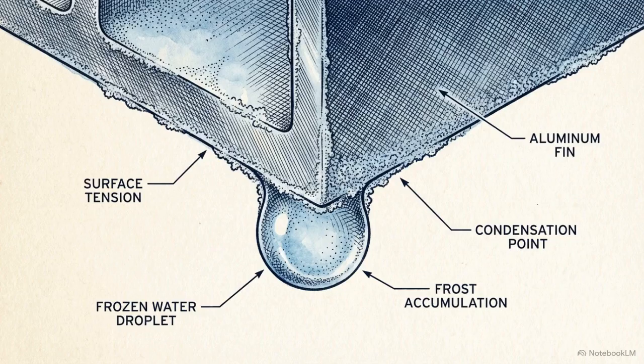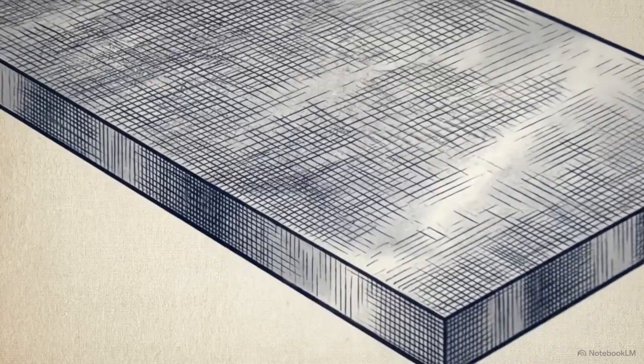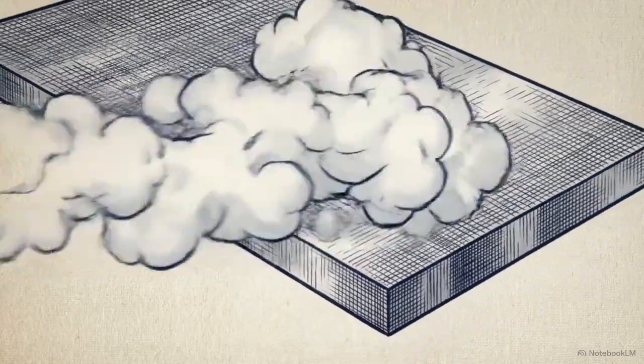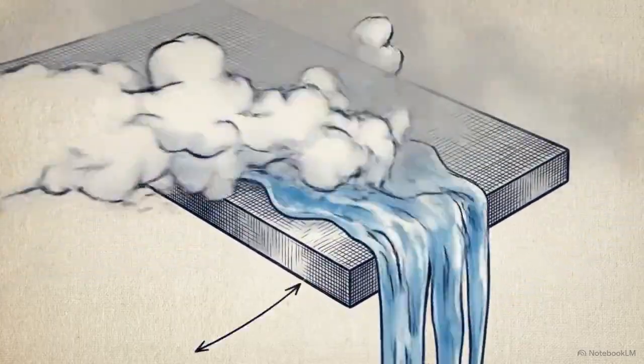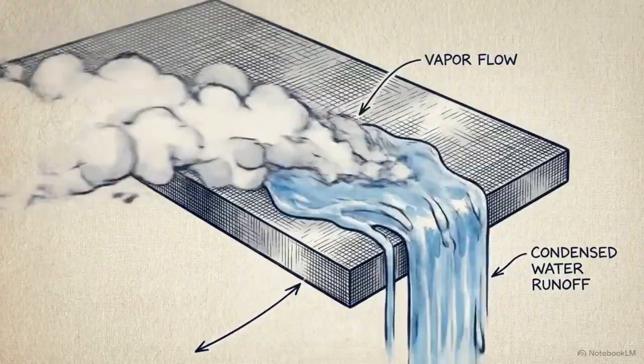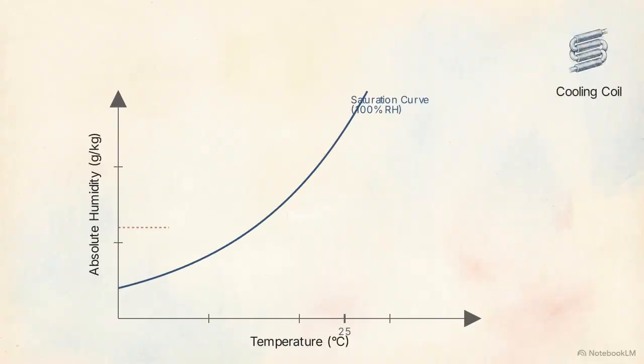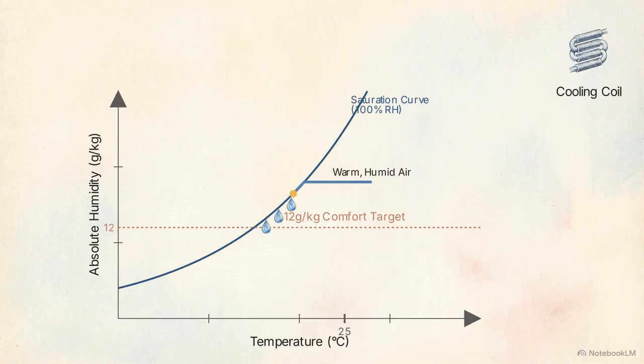Relying on dry bulb temperature sensors to control indoor moisture in an ultra-low energy building will always fail. To actually remove moisture, physics dictates a strict rule. Air must be cooled below its specific dew point. The dew point is exactly the temperature at which airborne water vapor instantly condenses and transforms into liquid water. This chart shows that reaching our 12 grams per kilogram target requires the cooling coil to aggressively drop the air temperature down the saturation curve to roughly 15 degrees Celsius.